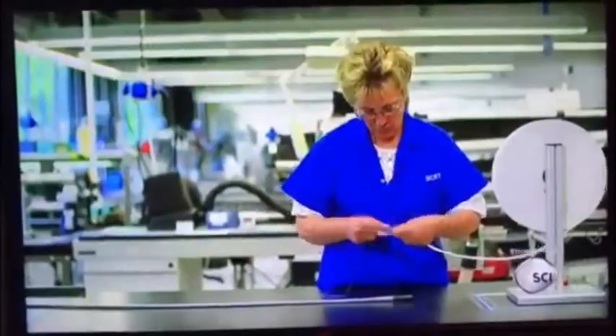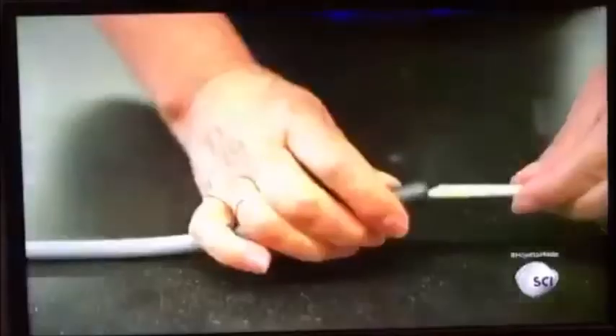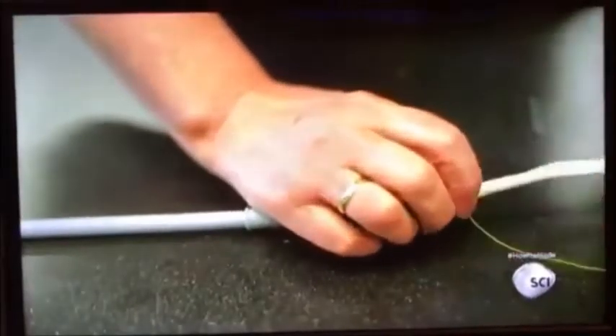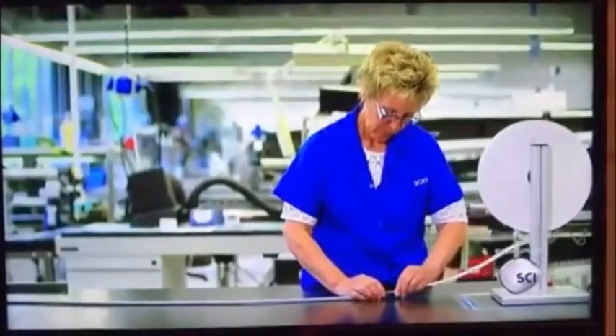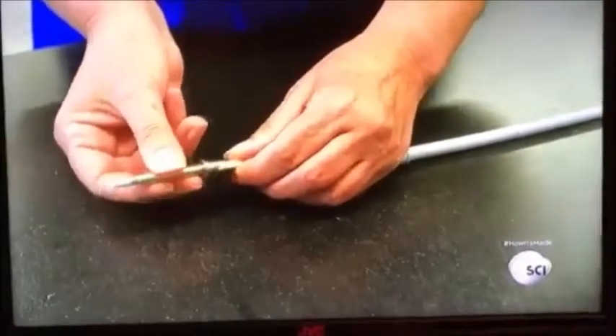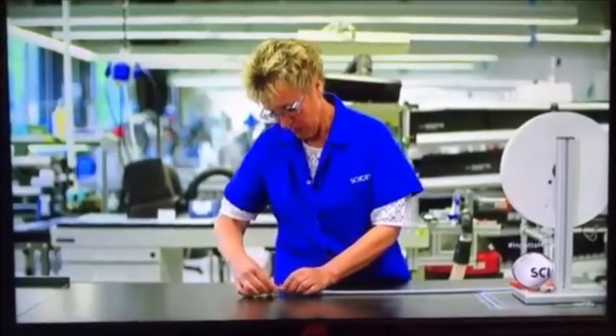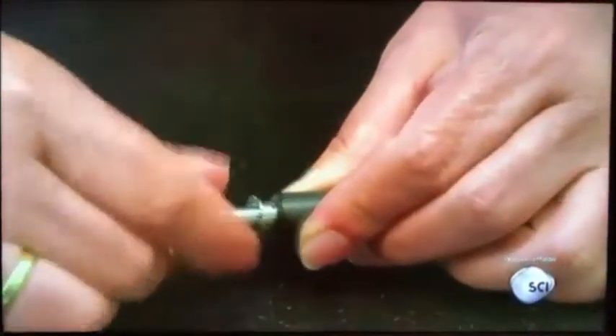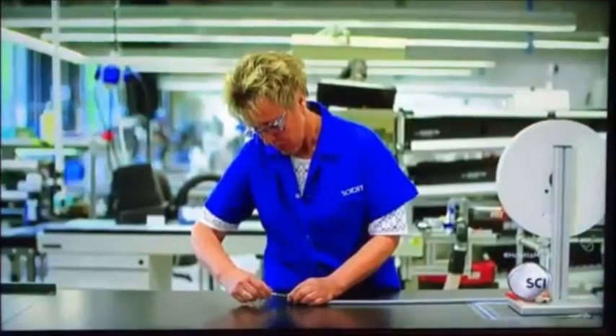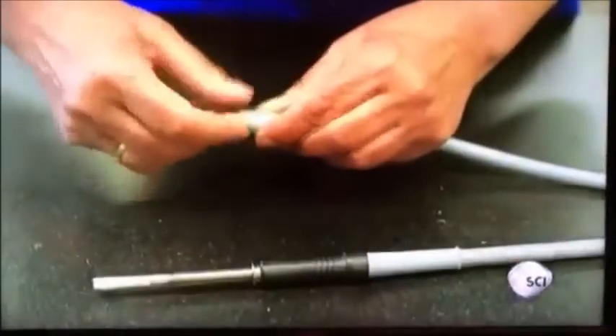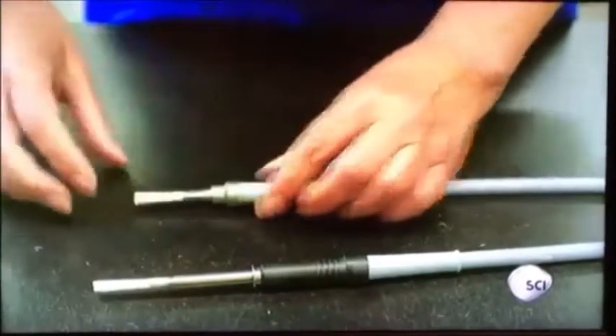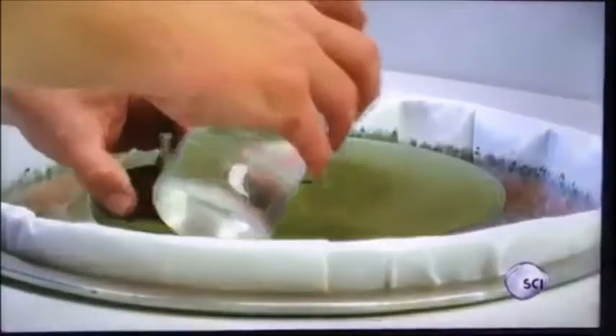To make the cable that connects a light source in the operating room to the endoscope, a worker inserts an optical fiber bundle into a silicone cable sheathing. This one has nearly 9,000 fibers. She screws a stainless steel fastener called a ferrule onto each threaded end of the sheathing. After saturating the ferrules and optical fibers inside with glue and curing the adhesive with heat, the worker trims off excess fibers and hands off the cable to the next station, where a worker polishes both ends.